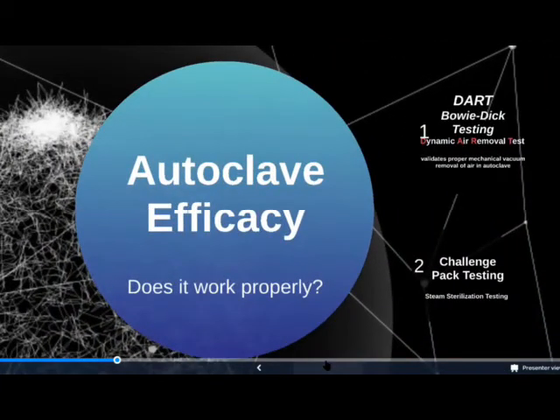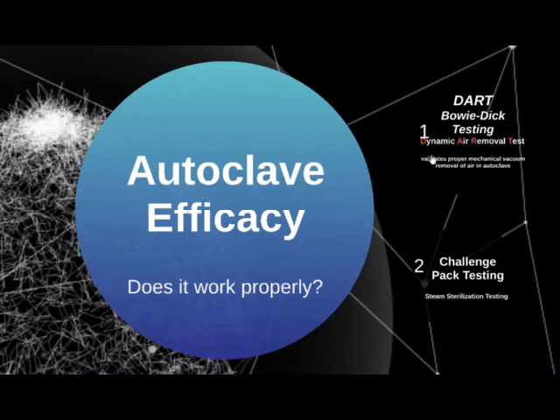So autoclave efficacy is checked daily, and the nurses upstairs are looking in the IUSS logs to see if they can actually utilize the autoclave for that day. Each day, the Bowie-Dick test, also known as the dynamic air removal test, validates proper mechanical removal of the air in the autoclave chamber. The challenge pack is testing the steam.